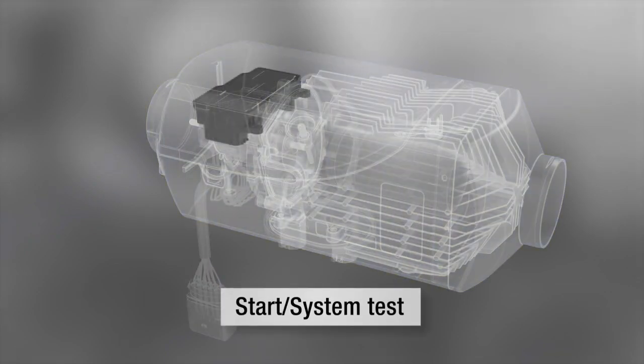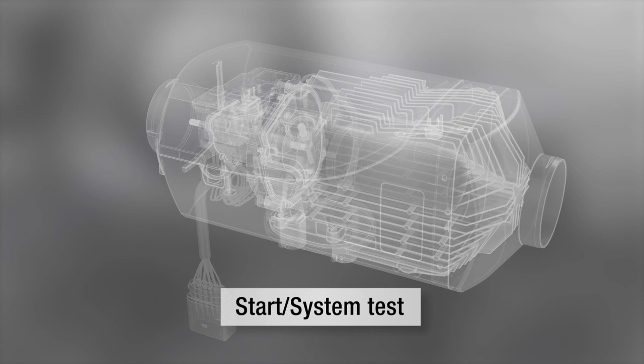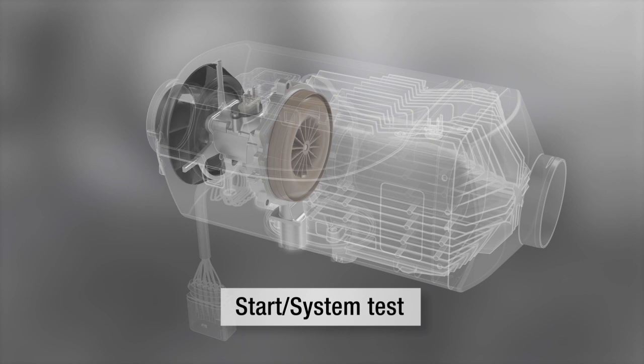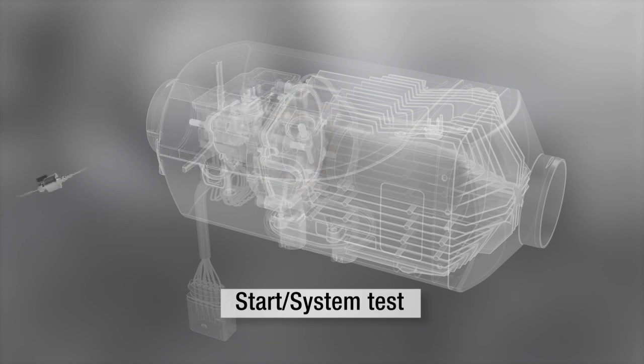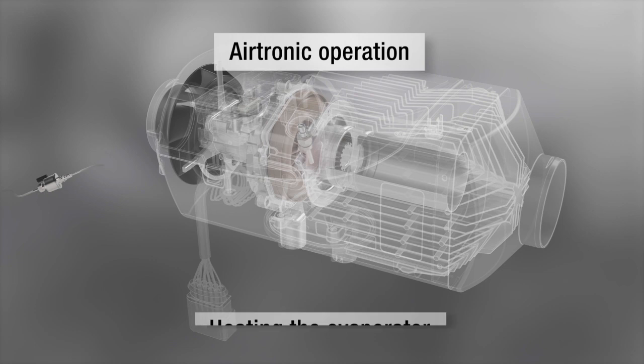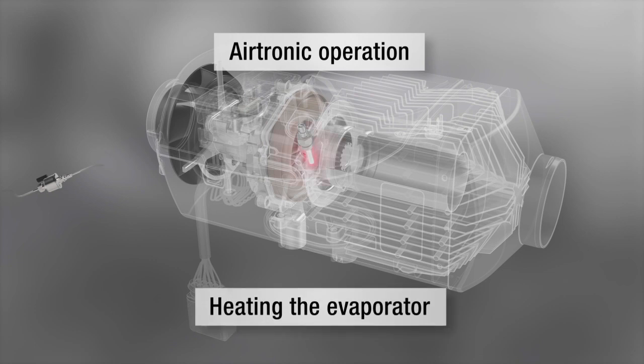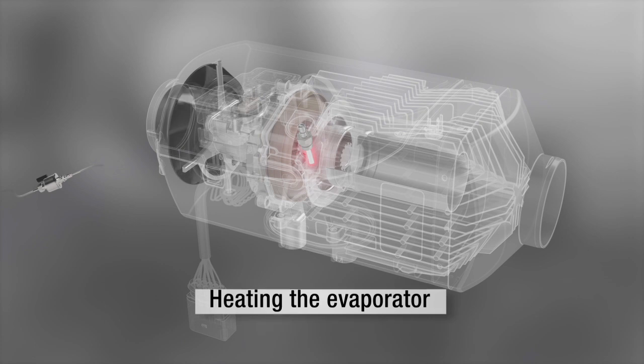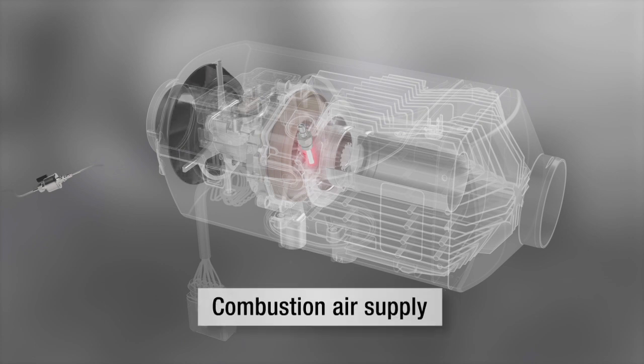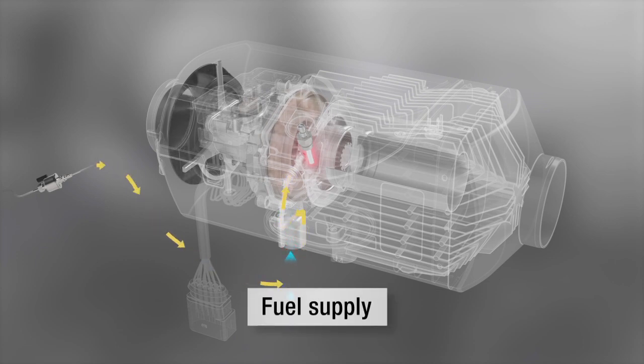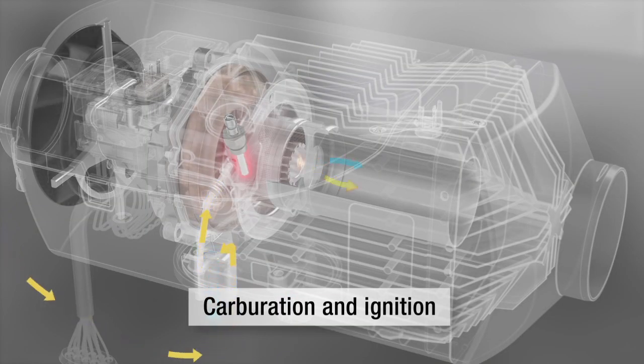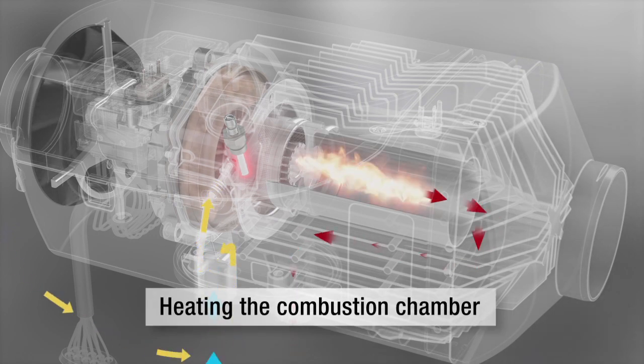When it starts up, the heater automatically runs a system test. The glow pin heats the evaporator in the combustion chamber. The fan impeller starts up and blows air into the combustion chamber. The fuel metering pump supplies fuel which evaporates in the evaporator, mixes with the air and ignites in the combustion chamber. The flame spreads evenly through the combustion chamber.